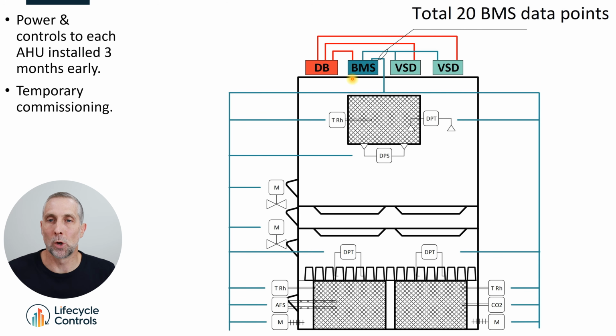And if you have a network controller on that trolley, you can power up the network control temporarily, suck all these BMS points into the network controller, and you can commission the database, the alarms and trends, the graphic could be on your laptop, you could check the binding, you could do the whole thing. There's a massive amount of pre-work that you could do on this temporary commissioning.